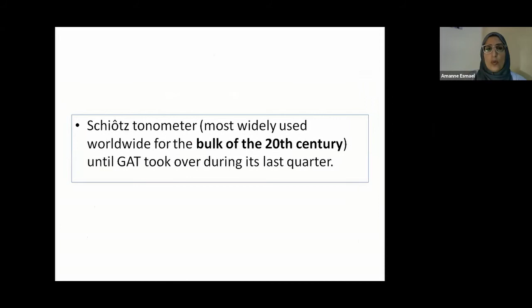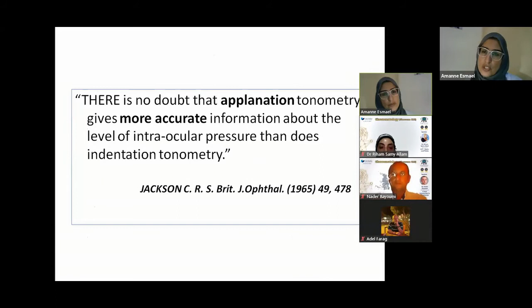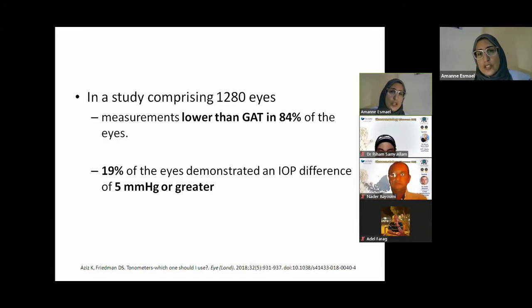So why is Schiotz not used right now as much as applanation tonometry or the Goldmann applanation tonometer? It has been well established since 1965 that applanation tonometry gives more accurate information about the intraocular pressure. Several studies have shown that the discrepancy between both devices' readings can be as large as 5 millimeters mercury or greater. And usually the Schiotz tonometer, in the majority of cases, will give an underestimation when compared to GAT.